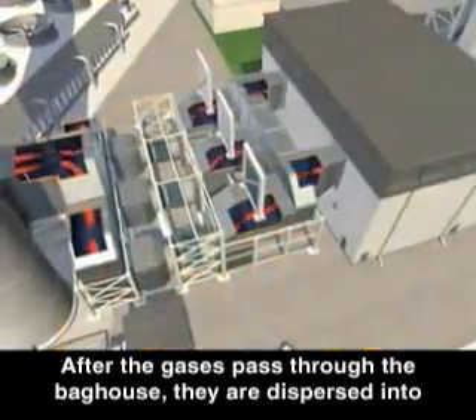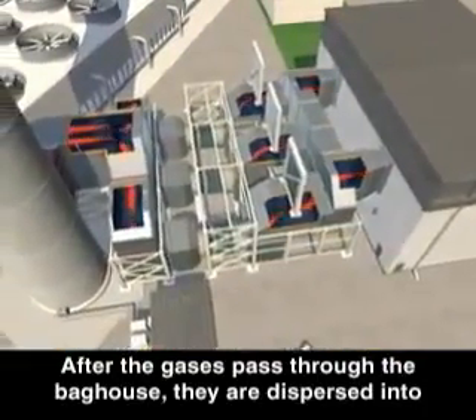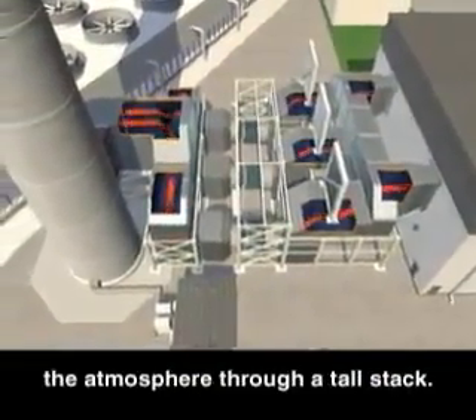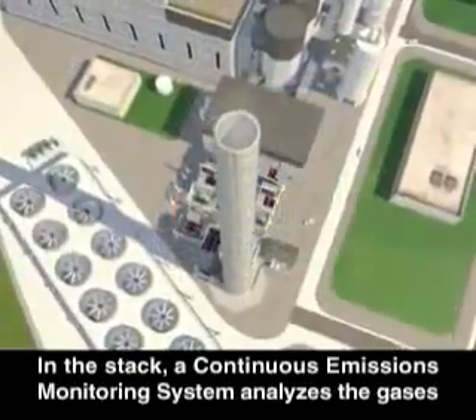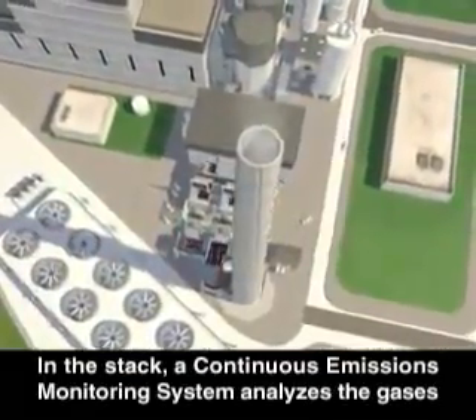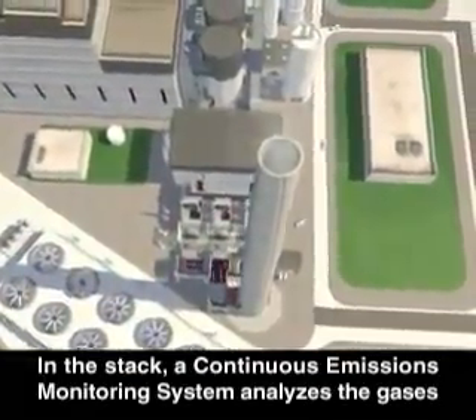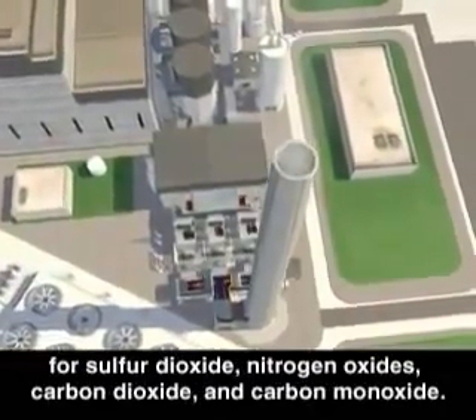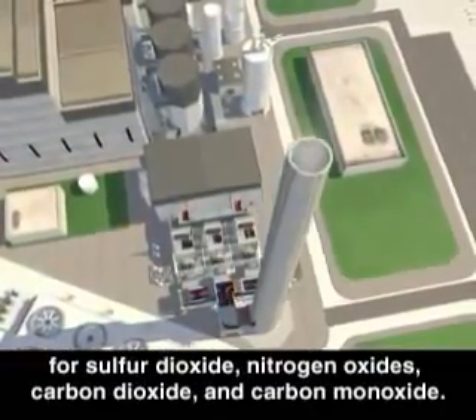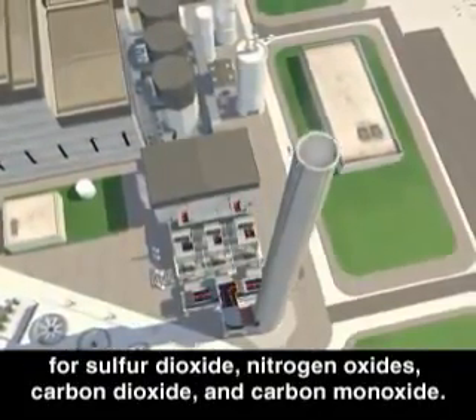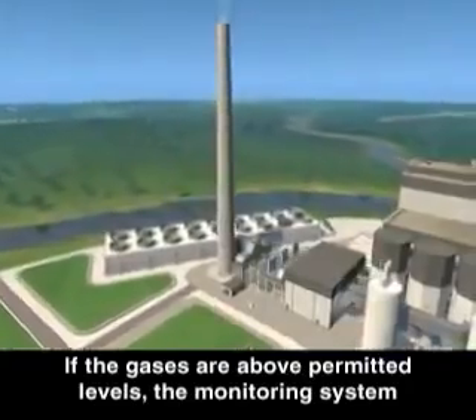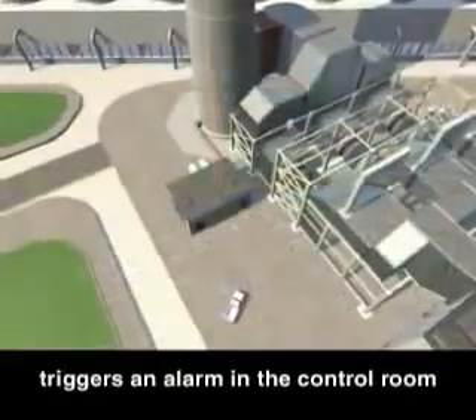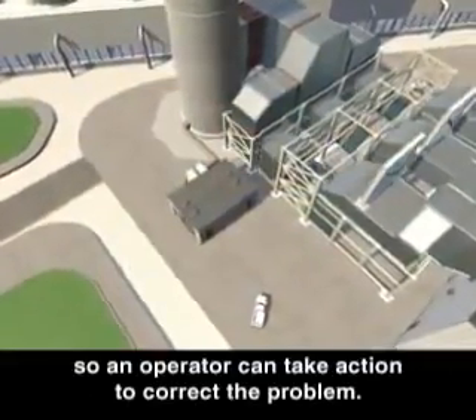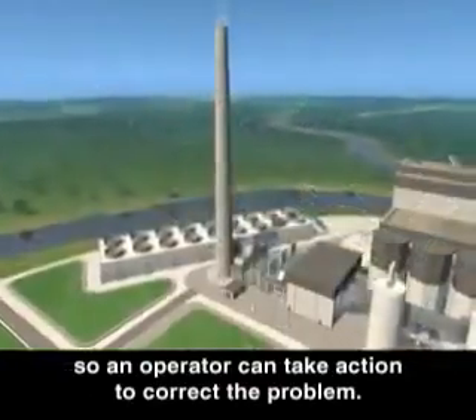After the gases pass through the baghouse, they are dispersed into the atmosphere through a tall stack. In the stack, a continuous emissions monitoring system analyzes the gases for sulfur dioxide, nitrogen oxides, carbon dioxide, and carbon monoxide. If the gases are above permitted levels, the monitoring system triggers an alarm in the control room so an operator can take action to correct the problem.